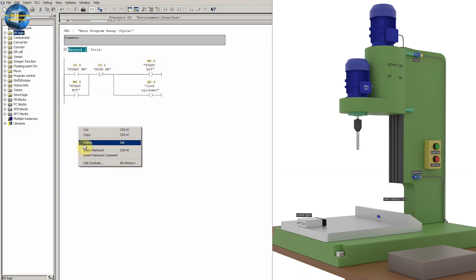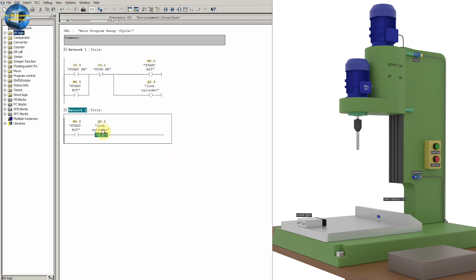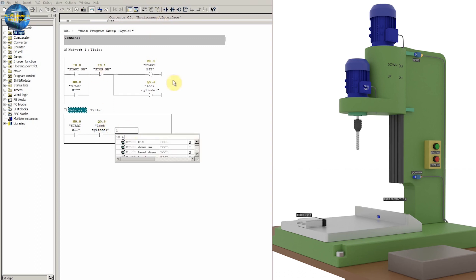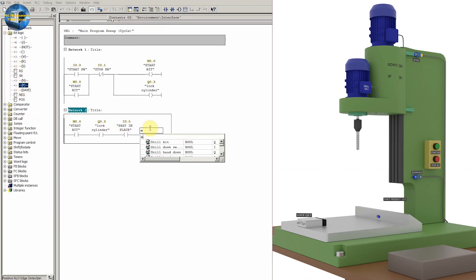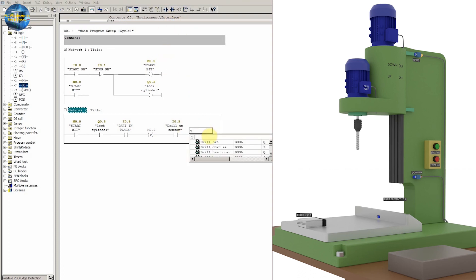In network two, when the start bit M0.0 is on, lock cylinder Q0.3 is locked, and the object is in place confirmed by sensor I0.5 on the rising edge detected by bit M0.2, and if the drill head is at the top position confirmed by sensor I0.3, we will turn on the drill head down output Q0.0.